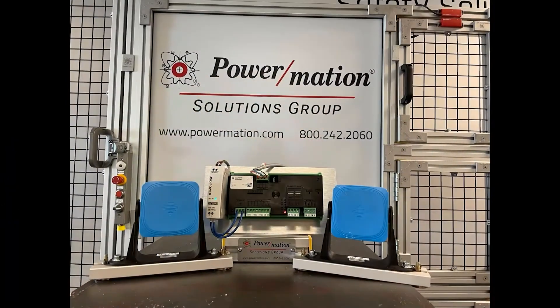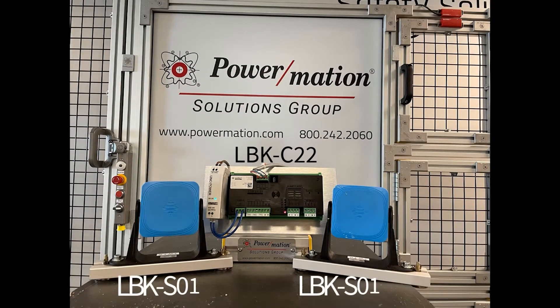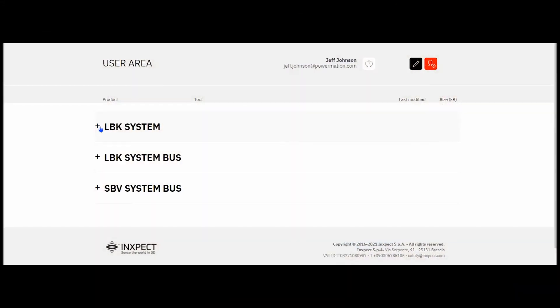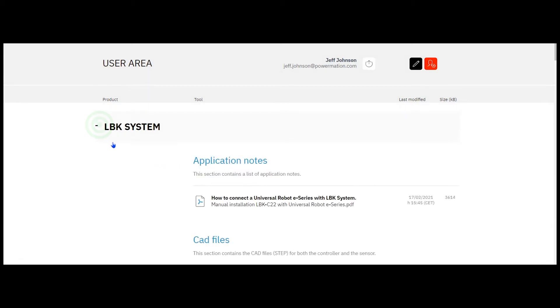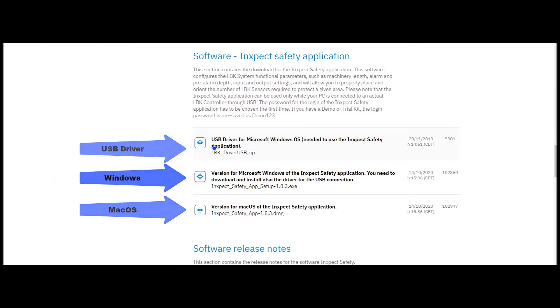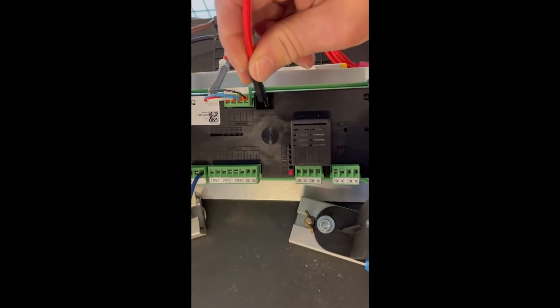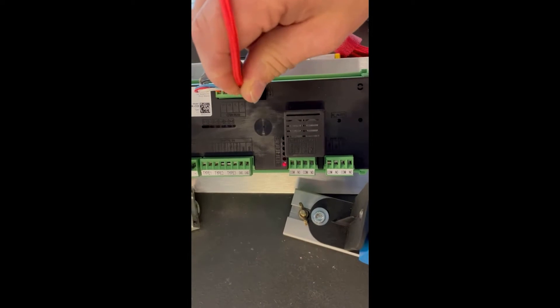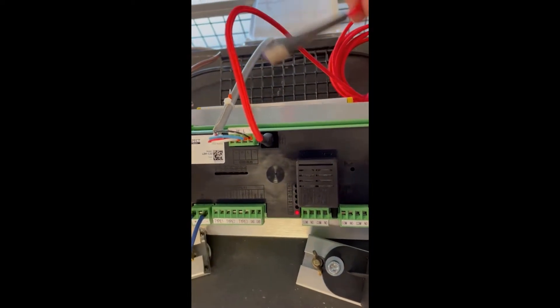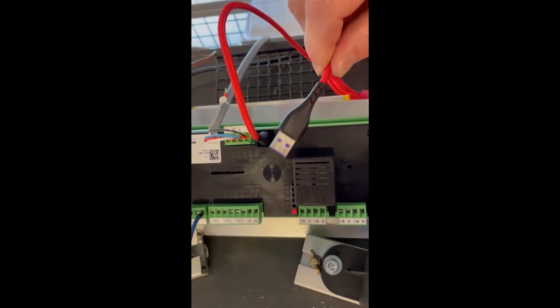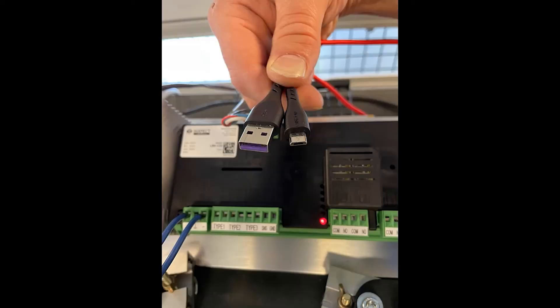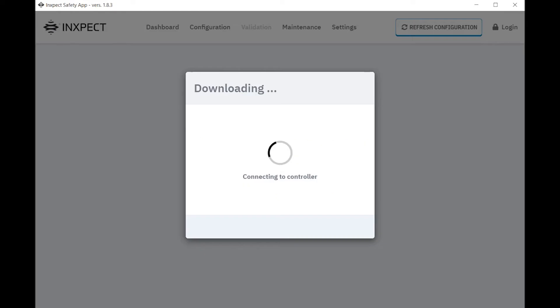We're going to be configuring an LBK C22 controller with two LBK S01 sensors. Before we get started, we'll need to download the USB driver and the software for the LBK controller. The Inxpect safety application can be downloaded for free and can be used in both Microsoft Windows and macOS operating systems. Once the driver and software is downloaded, the software can only be used while your computer is connected to a powered LBK C22 controller through a standard USB to micro USB cable. Once connected to the controller, we can run the Inxpect safety application.